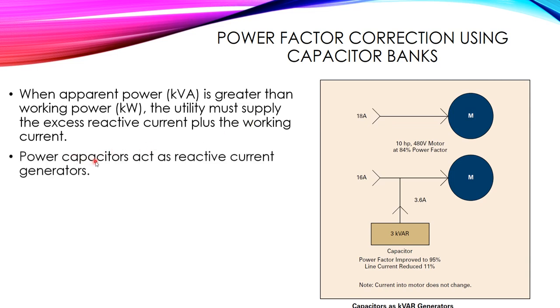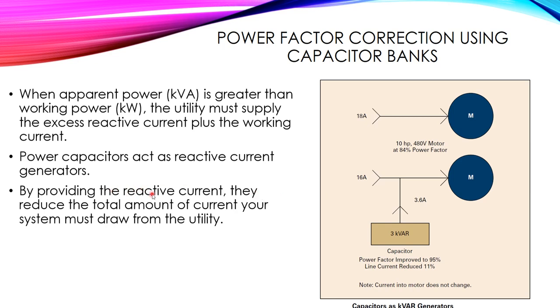Capacitors act as a reactive current generator — a source of reactive current — so the reactive current required from the grid is reduced. The current reduced from 18 amperes (active plus j reactive) to 16 amperes. By providing reactive power using the capacitor bank, you reduce the total amount of current your system must draw from the utility.